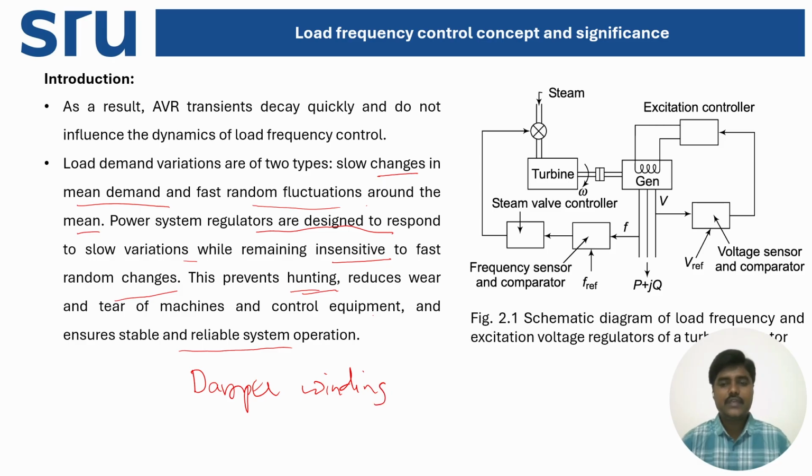So in the case of synchronous generator, this damper winding is placed in the slots made in pole shoes. If you go to the internal of synchronous machine, inside the pole shoes, we will make some slots, and there we are going to insert hard drawn copper bars, which are nothing but damper bars or damper winding. And this damper winding is also called as amortisseur winding.